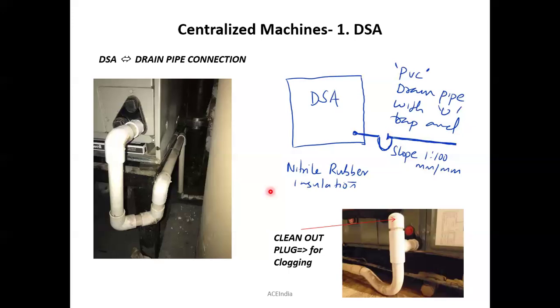Lastly, we need to consider one more factor, which is the insulation of these pipelines, especially the copper pipelines as well as the drain pipe connections. The drain pipe carries the water, which is condensed from the water vapor in the return air and fresh air when it contacts the evaporator coil, and these water droplets have a temperature of around 5 degrees, 6 degrees, even 4 degrees Celsius, isn't it? The drain water is comparatively colder than room temperature water. So as the water starts to flow across this drain pipe connection, what will happen?